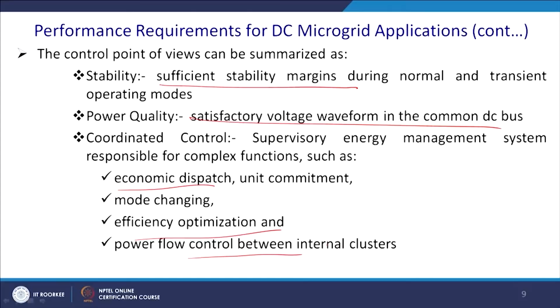Coordinated control, which we have discussed earlier, is also required. A supervisory energy management system is responsible for the complex functions. These may concern the power system, the microgrid, time duration, and unit switching. So, we have to consider these items also. These are economic dispatch, unit commitment, changing of mode for aligning to the grid connected mode and vice versa, efficiency optimization, and power flow between the two internal clusters. Those are all required to be featured in coordinated control.